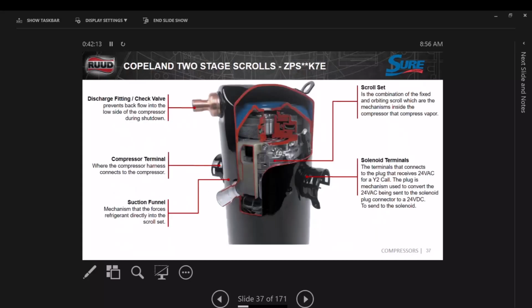As you can see the internals here, I've got one over here broken you can look at too. I'll show you, I'll even tell you what caused that. But here's your scroll set, and then right at the outlet of the discharge line, there's a check valve in there. If you're ever changing a scroll compressor, keep that valve very cool. In other words, wrap a wet rag tight around it, keep it wet.